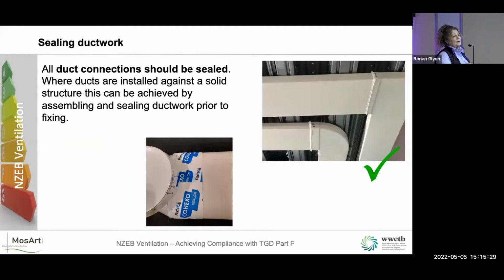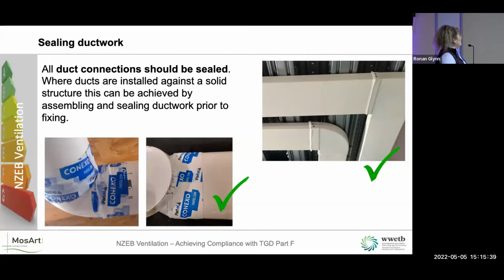So you use your applicator card and you take all the wrinkles out of it and you make sure the connections are taped up tight. Over here then we have, okay, it's taped up tight, it's wrapped around, like whoever was wrapping it definitely didn't pay for it. So there's 2.5 times too much tape on that. They never use an applicator card to smooth down the wrinkles. When you smooth down with the applicator card, the glue in the airtight tape starts to go off, and it goes off for 24 hours and then it's at its stickiest. So if you don't activate that, you might as well be putting sellotape on it.